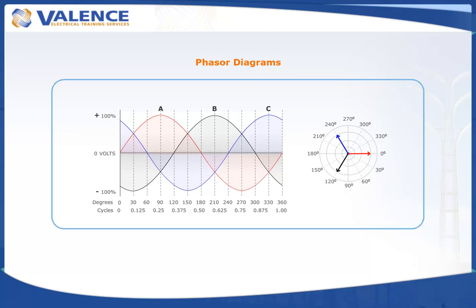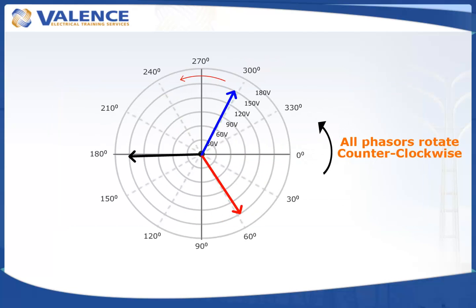The most confusing aspect of phasor diagrams is that it seems that nobody can agree on what phasor angles to use. Different parts of the world use different color codes, different standard voltages, different CT secondaries, different phase rotations, and different phasor angles to describe the same system. The only thing that the industry seems to agree on is that all phasors rotate counterclockwise.